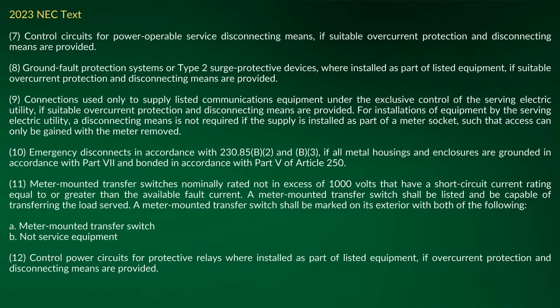Now, as you look at 230.85, that's where I pick up my emergency disconnects, and this is going to deal with 1 and 2 family dwellings. And if you look at B3, we'll look at B2 and B3, but it says each disconnect shall be one of the following. You got your service disconnect, and then you have a meter disconnect integral to the meter housing, and then you have another one, other listed disconnect switch or circuit breaker that is marked suitable for use as service equipment, but not marked as suitable only for use as service equipment, installed on the supply side of each service disconnect.